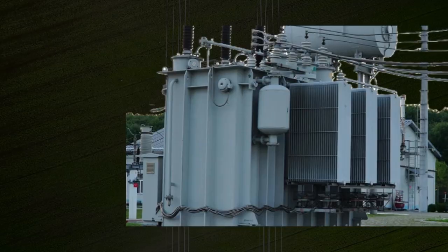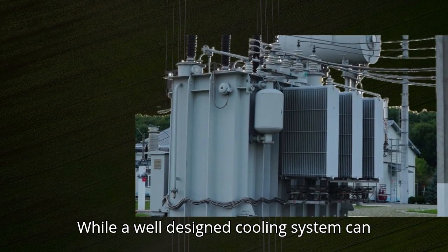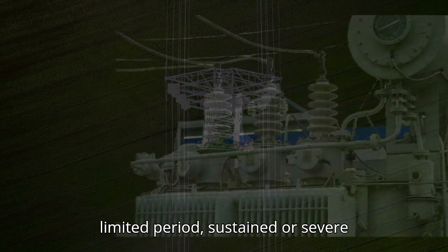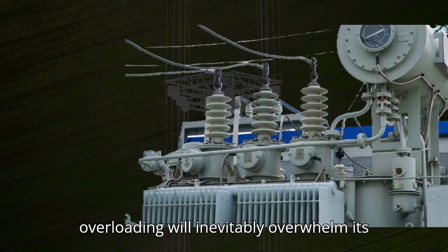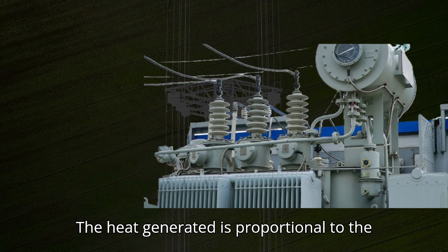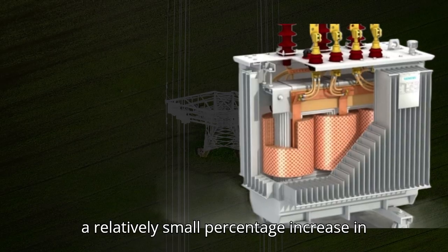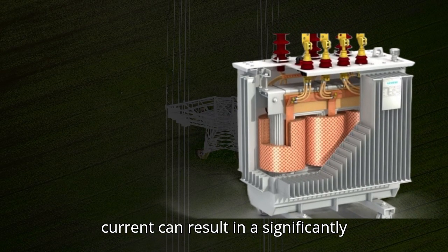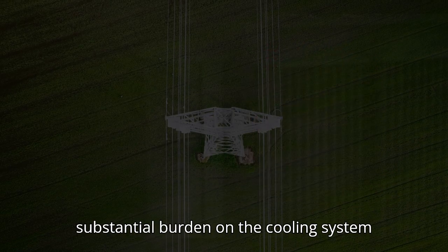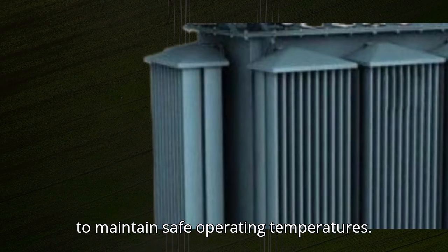The efficiency of the cooling system is directly challenged by overloading. While a well-designed cooling system can manage a certain degree of overload for a limited period, sustained or severe overloading will inevitably overwhelm its capacity to remove heat effectively. The heat generated is proportional to the square of the current, meaning that even a relatively small percentage increase in current can result in a significantly larger increase in heat, placing a substantial burden on the cooling system to maintain safe operating temperatures.